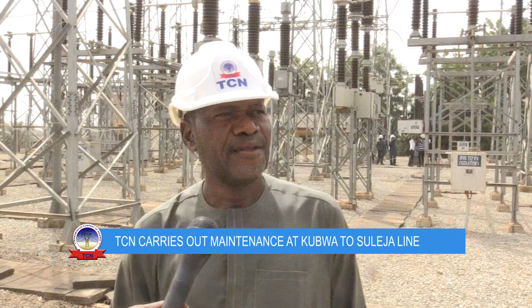We noticed changes in the insulation level of the transformer due to frequent Buchholz alarms. Every time, about two or three alarms were received, but no treatment was given at that time. So we decided that when we got the time, we would not take this for granted, because that's how we lost some of our transformers, as you can see. So when we got the time, we said let us carry out a thorough test and maintenance.